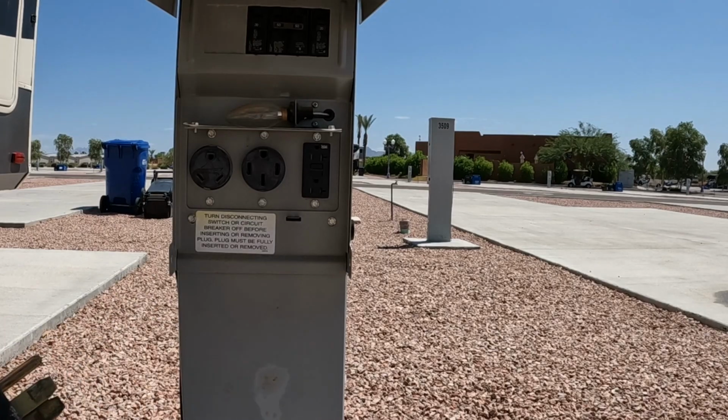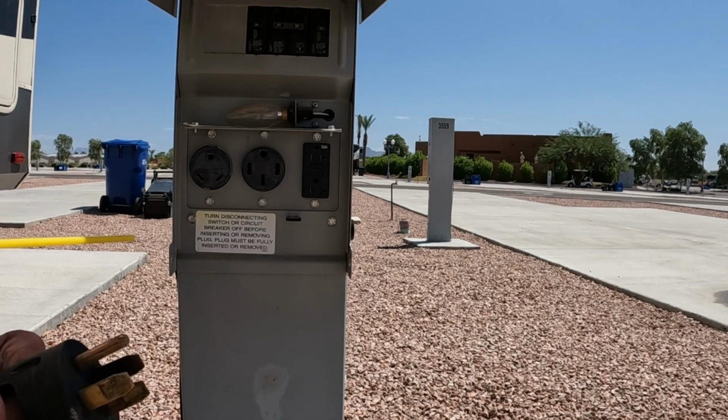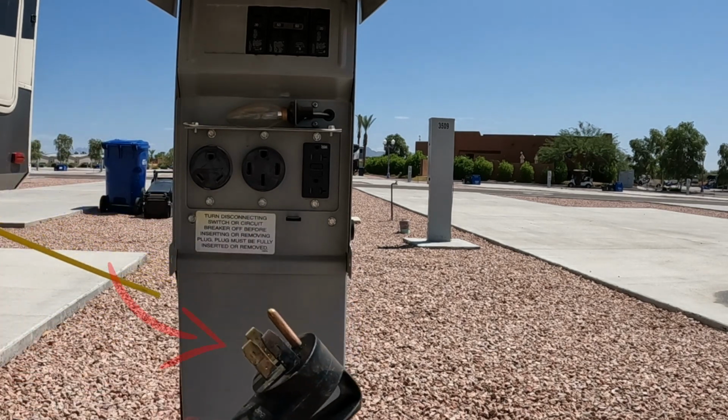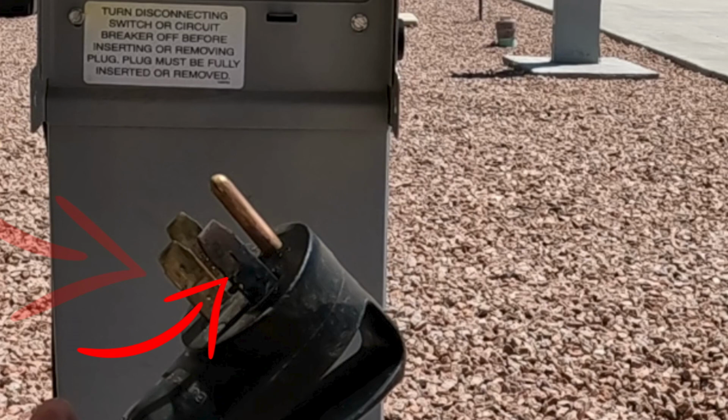At first, it looked fine, but something caught my eye. Notice the inside of those. One of them's actually kind of burned. Upon closer inspection, I could see that one of the 120 volt legs was badly carbon fouled, but the rubber of the plug seemed fine, so I cleaned off the carbon with a pocket knife and then shined the surface up with some emery cloth and wiped it clean with a clean cloth.